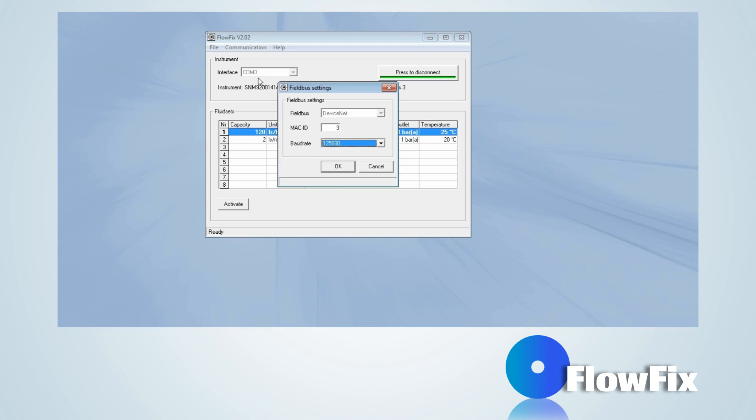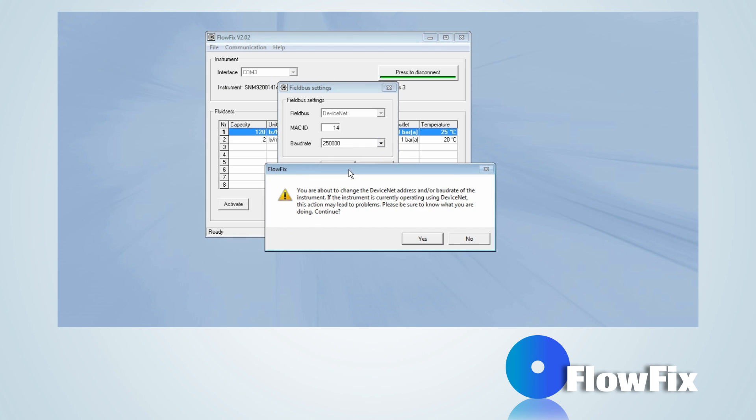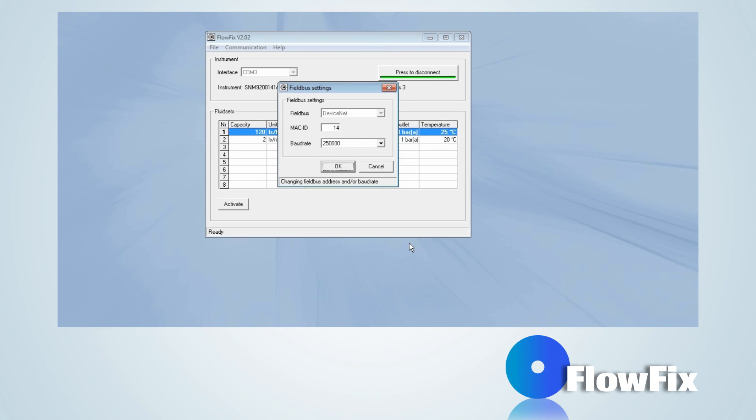In this example, the address of a DeviceNet slave, MAC ID, will be changed from 3 to 14 and the baud rate from 125,000 to 250,000 baud. Press the OK button, followed by the Yes button for confirmation.